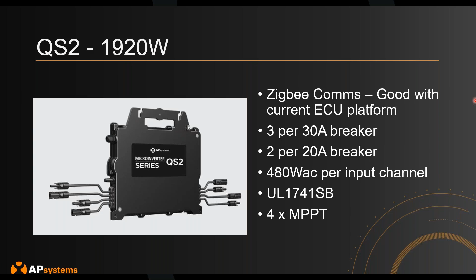I want to share this graph comparing the QS2 with the DS3Ls. If you look at these two lines, you can see that because the DS3Ls have smaller AC output, you can put more of these microinverters on a branch, and as a result more panels per branch as well. For a DS3L, you can put 14 panels on a 30 amp breaker, whereas the QS2 can put 12 on a 30 amp.